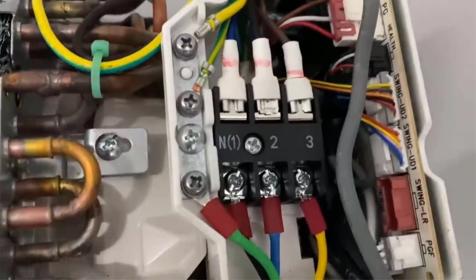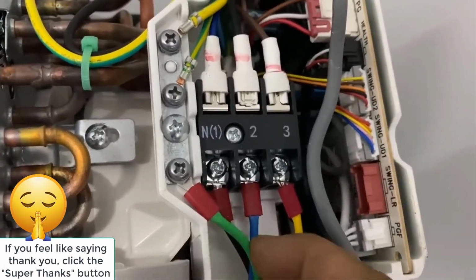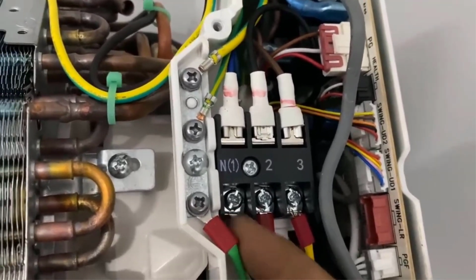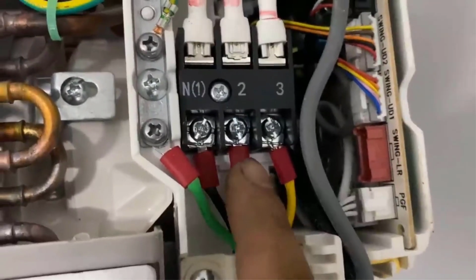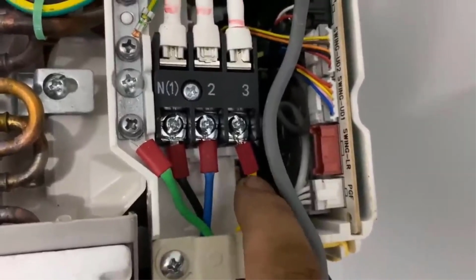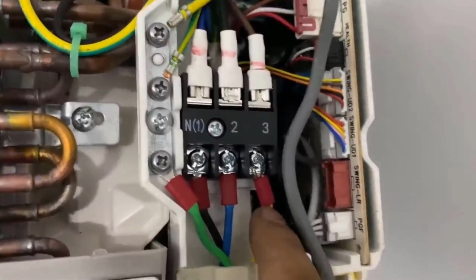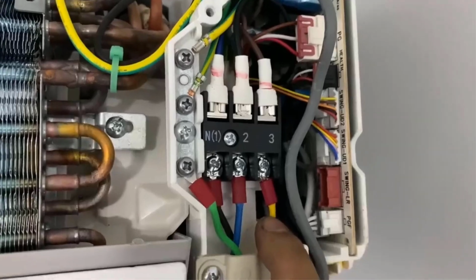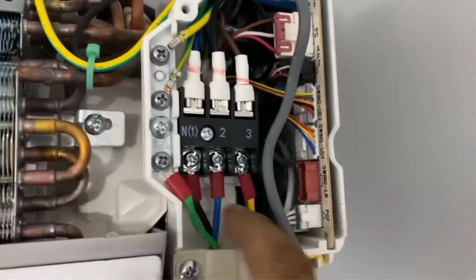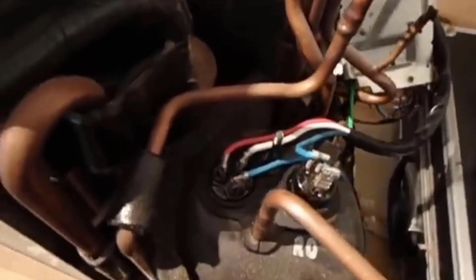What are the symptoms of this error? Air conditioning does not turn on. In some cases, the equipment may not start to operate due to this error. Intermittent operation. The air conditioner may turn on and off repeatedly or experience sudden changes in temperature. Strange noises. The compressor may make unusual noises during operation. Error codes. The air conditioner panel may display a specific error code related to zero crossing.